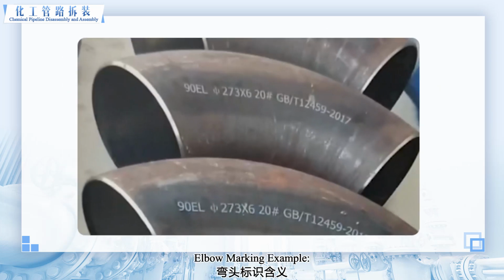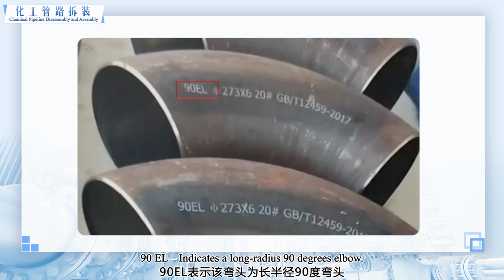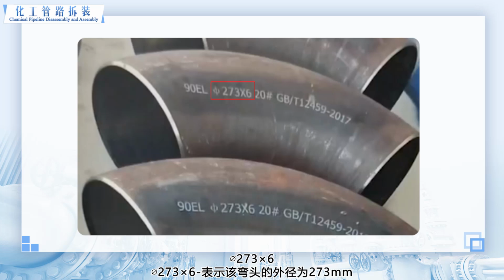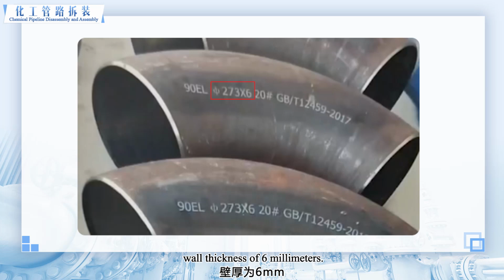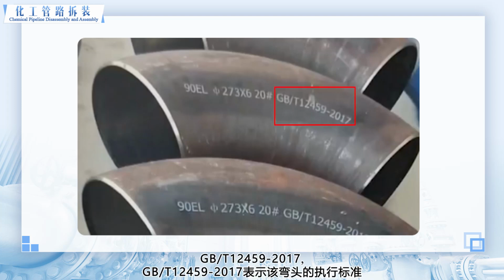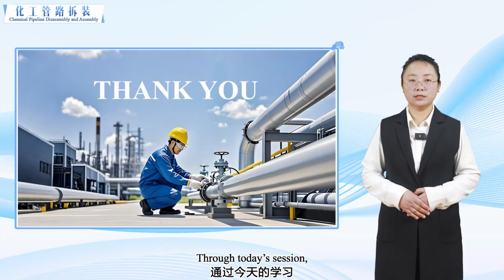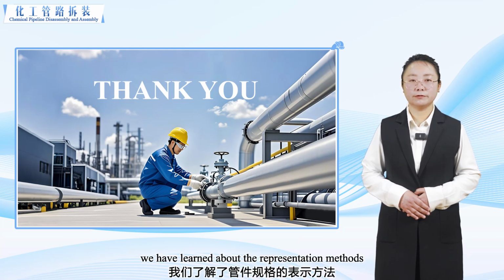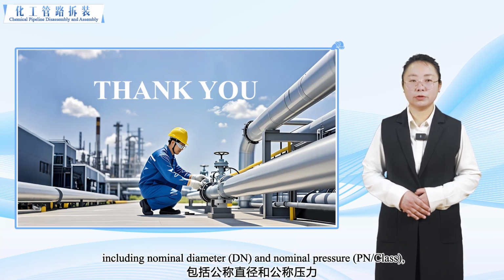Elbow marking example. 90 EL indicates a long radius 90 degrees elbow. 273 times 6: outer diameter of 273 mm, wall thickness of 6 mm. 20#: material is No. 20 carbon steel. GB/T12459 2017: standard compliance.